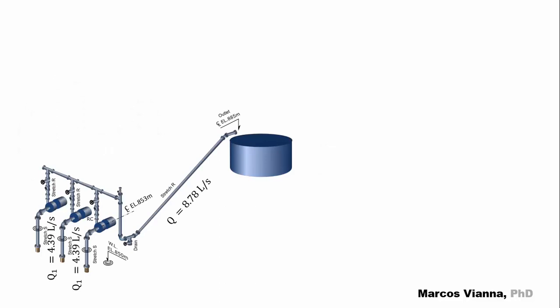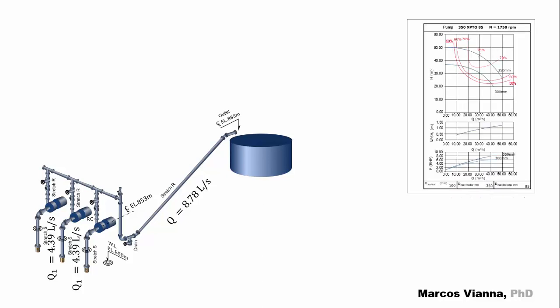Now, this is the system that we are studying: two pumps that run in parallel and a third one on standby. We know the pump chart, the total flow, and the contribution of each one of the pumps — that will be half of the total flow. For this contribution, we found that the corresponding required NPSH would be 0.65 meters.